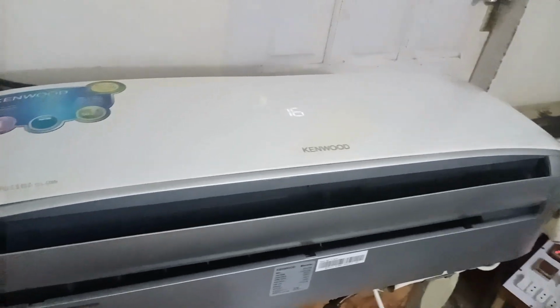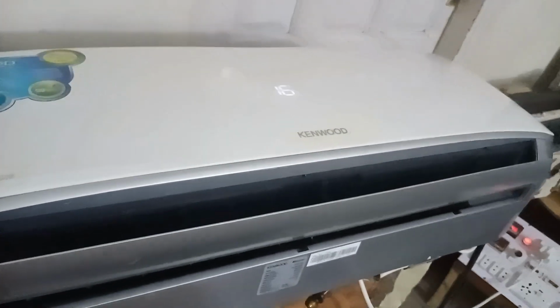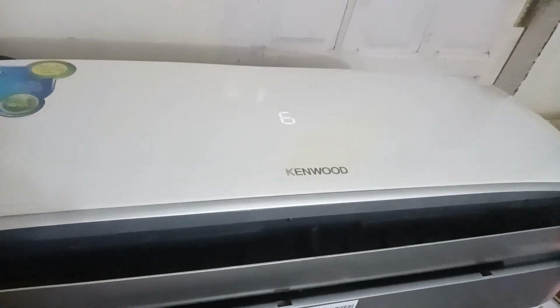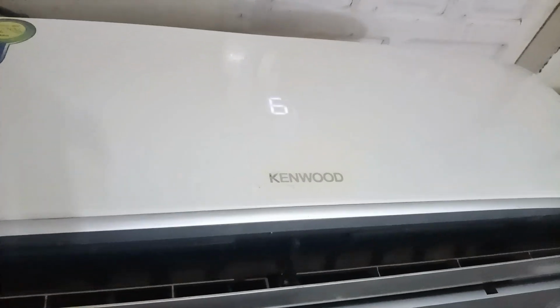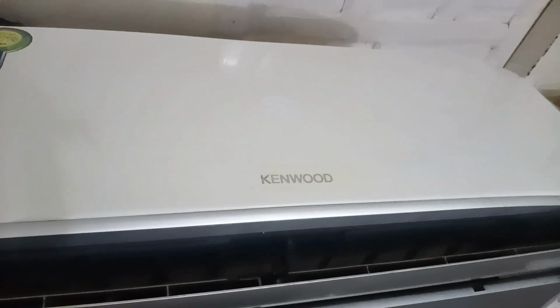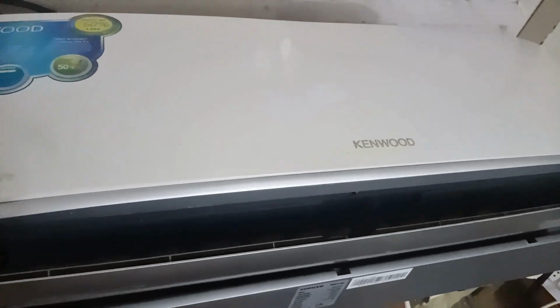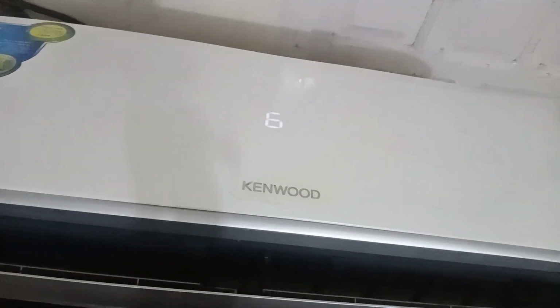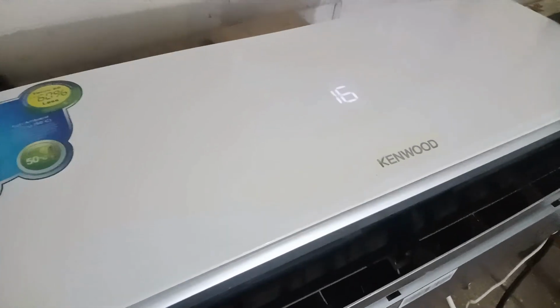The error has appeared on the display of the mini-split air conditioner. Sometimes it shows 16 and sometimes it shows 6. I will now explain in detail why this error occurs and what its causes are. The number 6 is the actual error code, while 16 is the set temperature displayed on the unit.